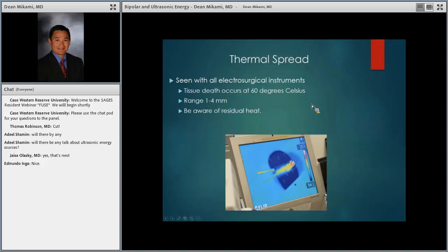So what are some of the clinical things we have to be careful with bipolar? Basically, we talked about this the entire webinar. We know that cell death occurs at 60 degrees Celsius. So we want to make sure that we don't have anything around that's going to be burned. This is a thermal image of a bipolar instrument, and these wires are actually 5 centimeters apart. So you see all the thermal injury or thermal damage that can occur even though you can't see it.